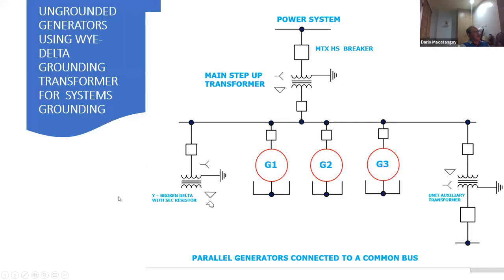Second type is the grounded one. In order to use ungrounded generators, what they sometimes do is install a Y delta grounding transformer. So, in a Y broken delta transformer here, this is your grounding transformer. These are your generators here. You see it's ungrounded here. And this is your unit auxiliary transformer, and your GSU.